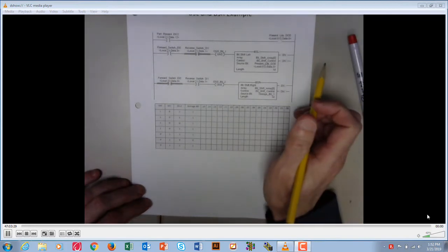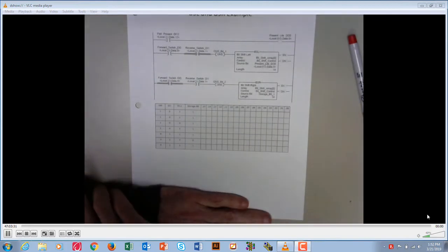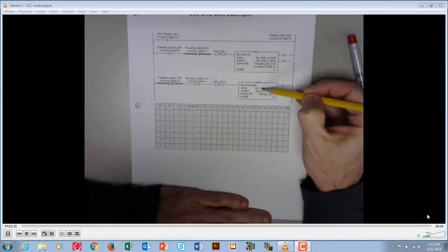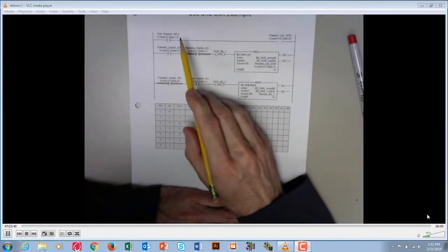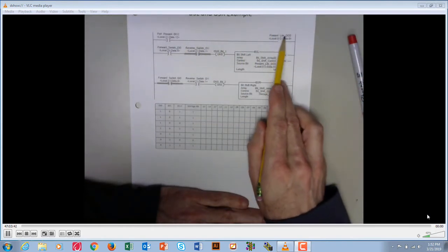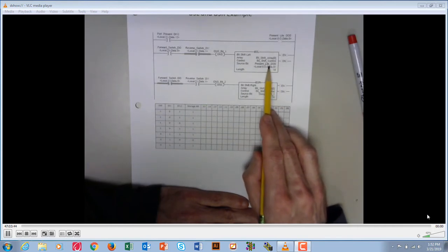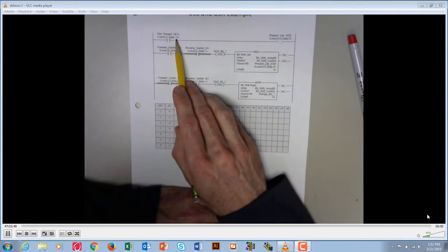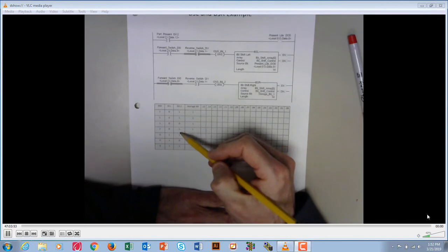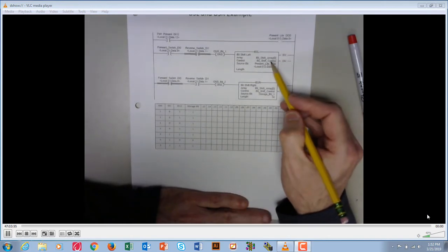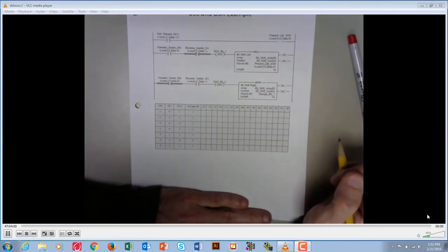Okay, let's take a look at this bit shift example here. What I have is I'm shifting left or I'm shifting right. The data that I'm pushing in here is the states of this light, so I'm pushing in zeros or ones. What turns this light on is input 12. So basically, if input 12 is on, that means that light is on and I would be pushing a 1 in on the left.